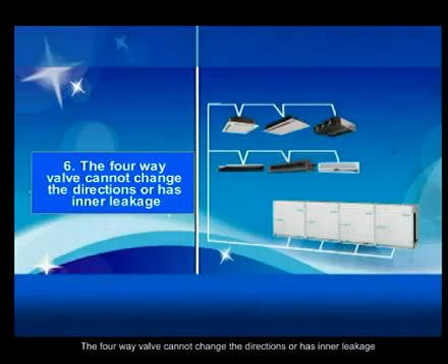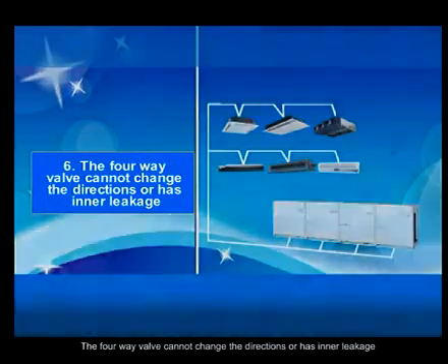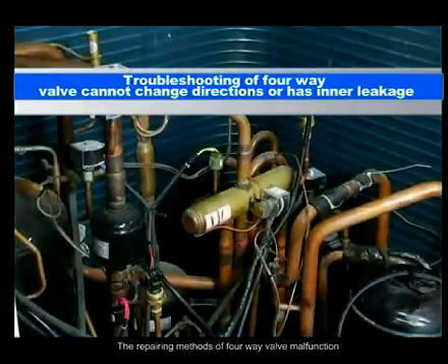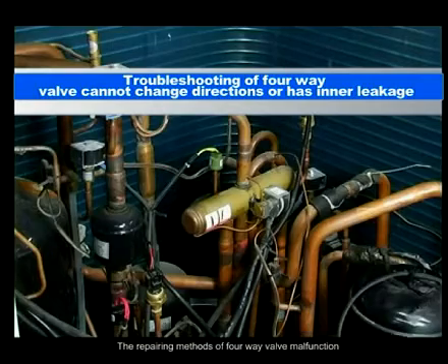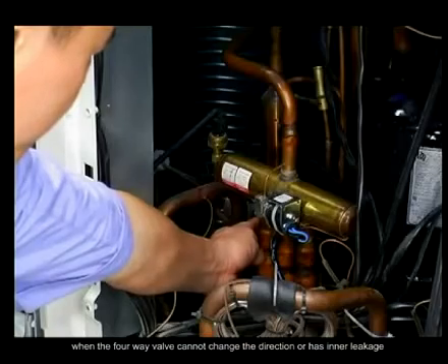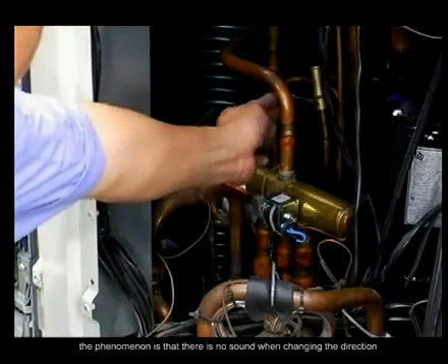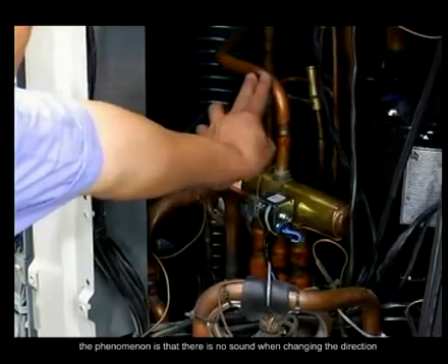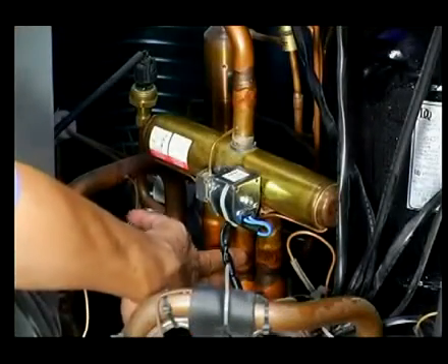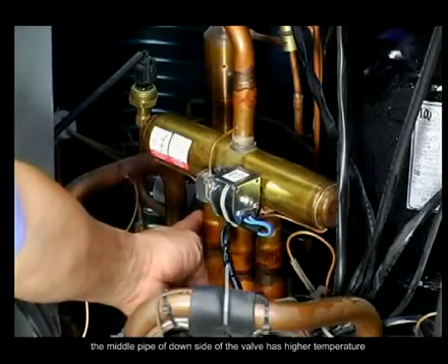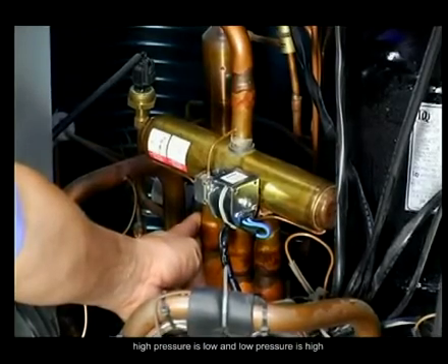The four-way valve cannot change direction or has inner leakage. The repairing methods of four-way valve malfunction. When the four-way valve cannot change direction or has inner leakage, the phenomenon is that there is no sound when changing direction. Cooling or heating performance is bad. The middle pipe on the downside of the valve has higher temperature. High pressure is low and low pressure is high.